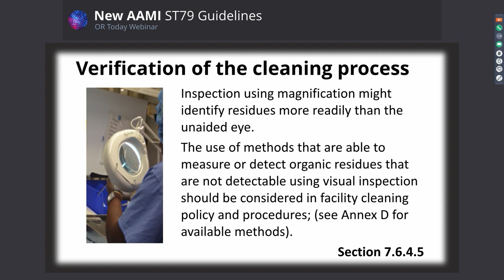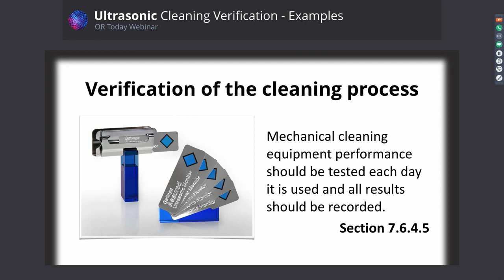Verification of the cleaning process can also include, say, for instance, the mechanical cleaning of equipment performance. You can use these metal coupons, that some people know as wash checks, and you put these in your ultrasonic machine while you are processing your instruments. And there is a blue soil that can become removed from these to show where you have had cavitation energy affecting the cleanliness of your instruments. You should be doing this each day, and all the results should be recorded. These can be easily recorded.